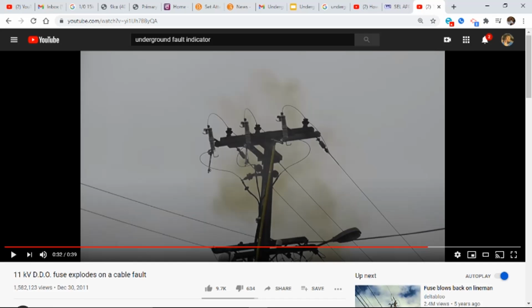Underground's a little bit different, gentlemen. When you go into underground, the engineer was telling me, those are 90% of the time permanent faults. What do I mean by permanent fault? Like you have to replace the whole wire or something? Yeah, something is wrong somewhere and it hasn't cleared itself. It hasn't fallen away. And we know that transformers are very, very reliable and very, very sturdy. So most of the time it's primary cable. And if you have a fault in underground primary cable, it doesn't go away.